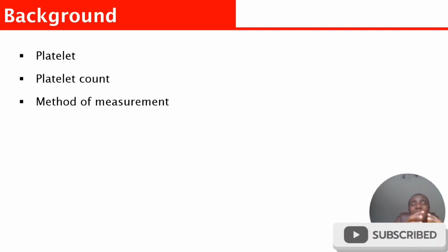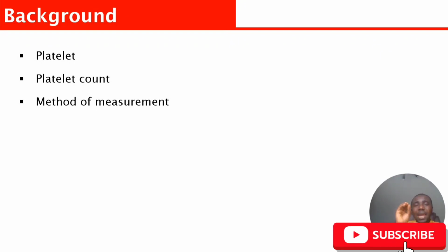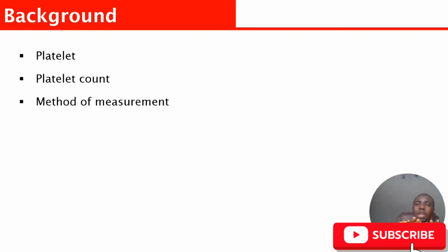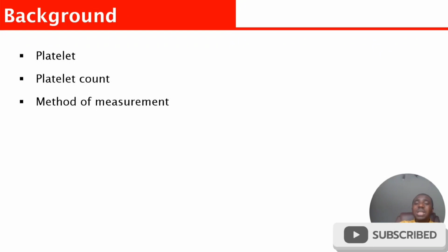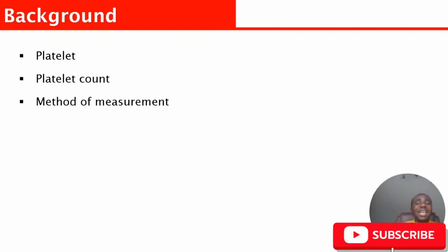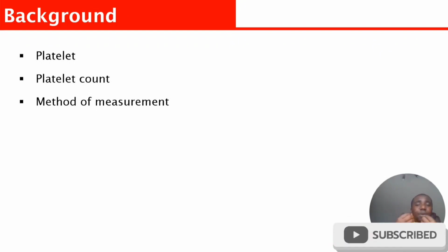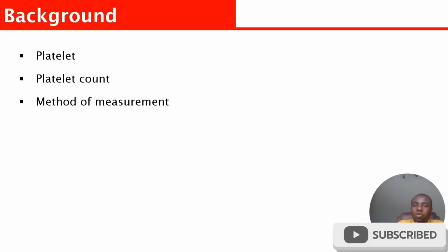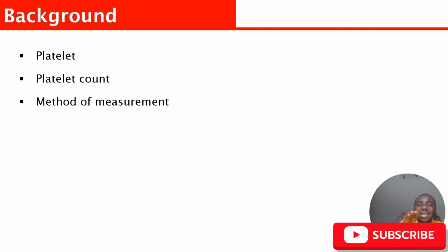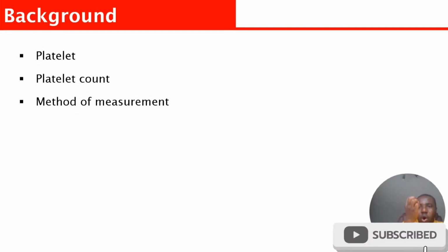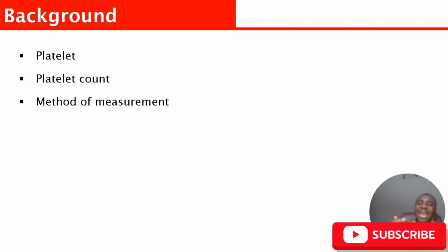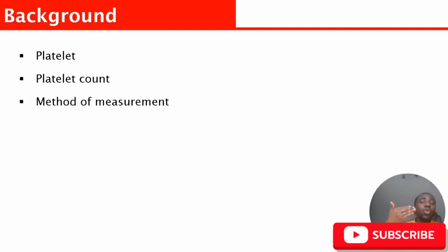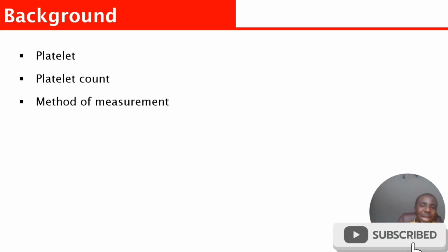So what it then means is this: when the analyzer aspirates the whole blood, some of the blood will then go to the channel that can analyze the platelet. So once the whole blood is lysed and exposes the platelet or thrombocyte, at some point this cell will need to pass through a hole which is called an aperture, and as it passes through the aperture, that is how the analyzer can count the amount of platelet.